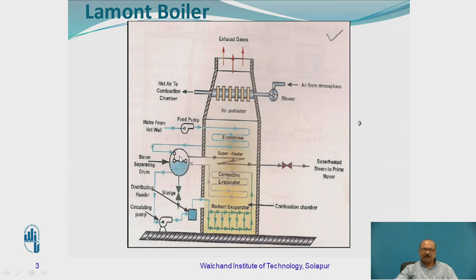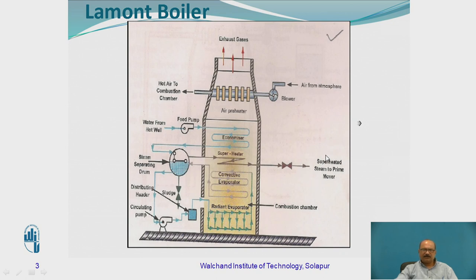Here the separation of steam is going to take place. This separated steam comes to the superheating stage. Water is available in the drum, but only the steam is going to be passing through the superheating stage — removing any final particles of water if present in the pipeline. The superheated steam is then supplied to the turbine, which we call the prime mover.